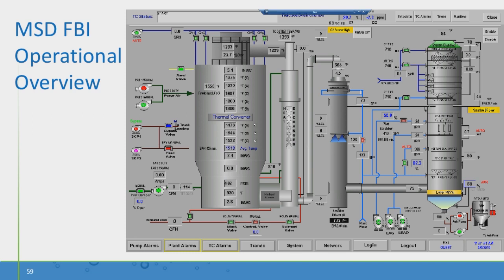Just beneath this, you will see our natural gas line and all of the accompanying valves that we use to regulate our natural gas flow into the incinerator, balanced with our air in accordance with our sludge flow as well. Kind of still in the left-hand corner, but about halfway up the screen, you'll see what are labeled as SCP-1 and 2. Those are our swing pumps that actually pump the sludge into the incinerator itself. So number 1 here was bypassed when this image was taken as we were shut down. But those are our 3 primary components: the carbon source of the sludge from the swing pump and the oxygen from the blower and the fuel source of the natural gas, all flowing in, mixing together.